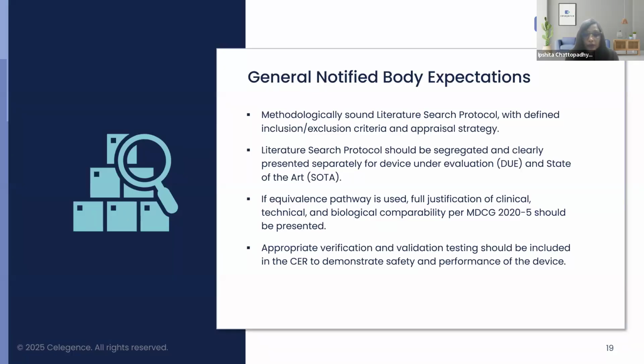So, manufacturers must show that the devices share similar design, materials, mode of action, and intended use, and that they have sufficient access to the technical documentation of the equivalent device also if required. So, notified bodies generally scrutinize these claims, especially for class 3 and implantable devices, and expect a clear, traceable evidence supporting each aspect of equivalence. And failure to meet these expectations can result in delays or, say, even in the rejection of the clinical evaluation.